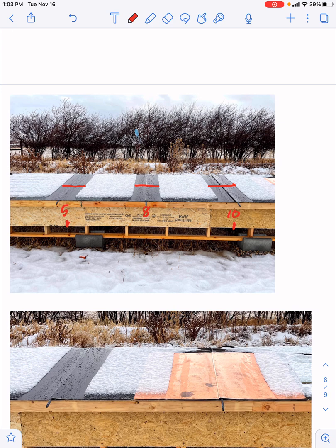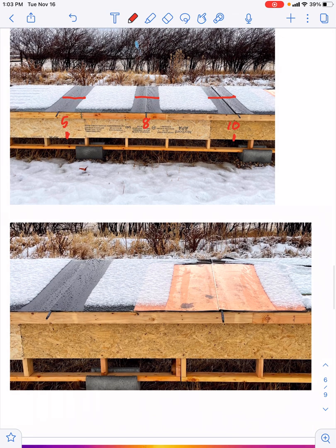But when we came down to looking at copper versus steel, huge, significant amount of difference. This right here on the steel was about a 10-inch clearing with one line of heat, whereas the copper, you can see, is significantly larger, and that ended up being, I think it was around 18 inches. So copper is definitely better in performance.